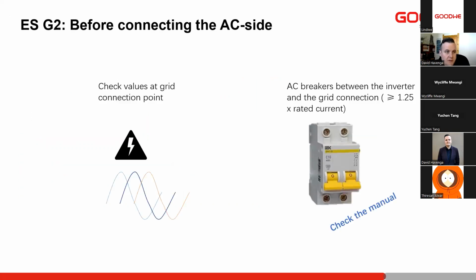It's always important, before connecting the AC side, to check the grid values and make sure that everything is correct. The AC breakers between the inverter and the grid connection are rated at 1.25 times the rated current. But I already have the recommendations for a few different models in one of my earlier slides.